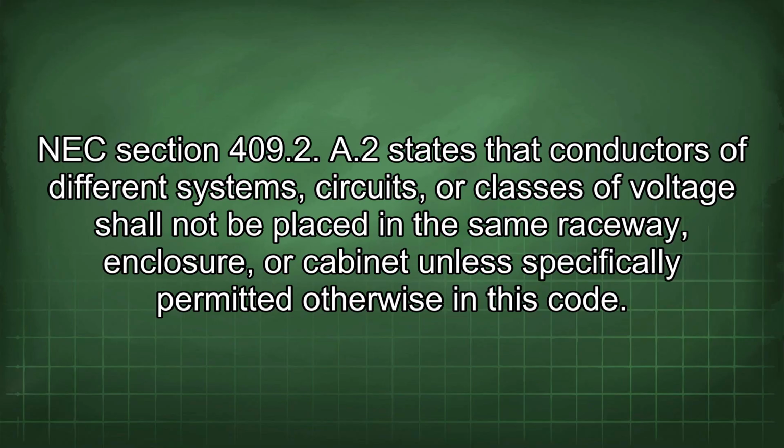NEC Section 409.2 A2 states that conductors of different systems, circuits, or classes of voltage shall not be placed in the same raceway, enclosure, or cabinet unless specifically permitted otherwise in this code.